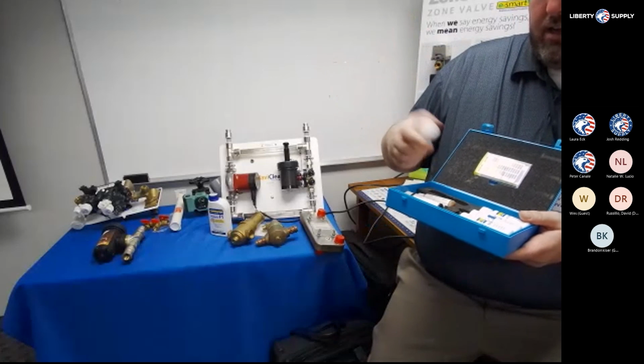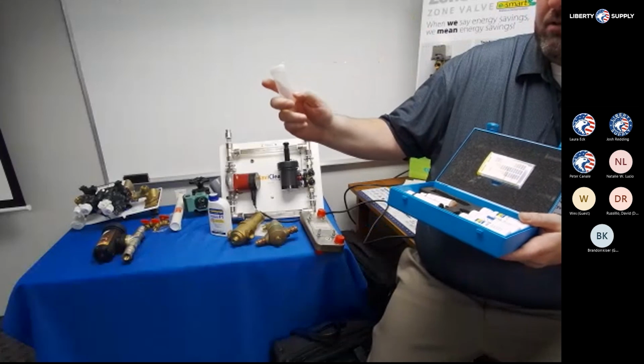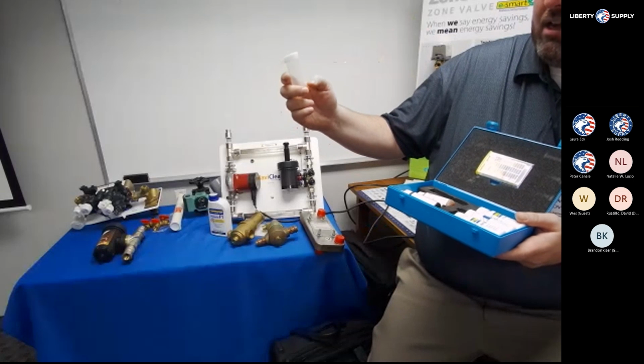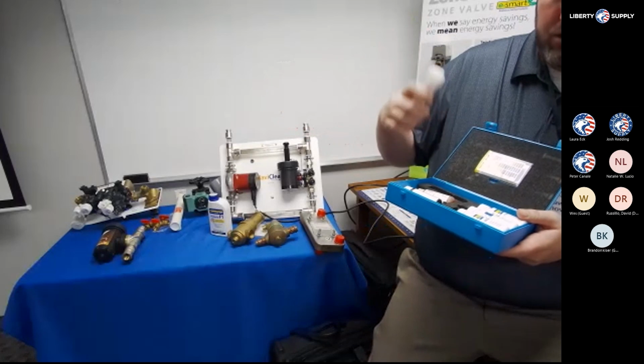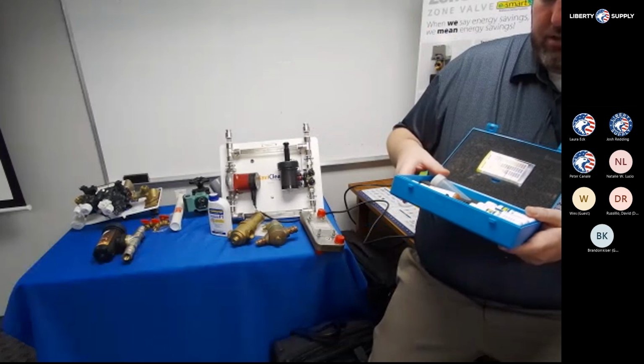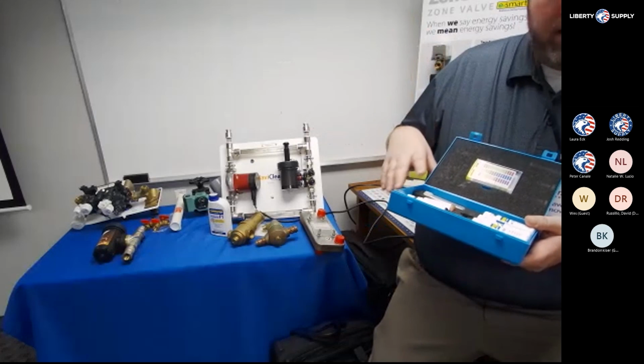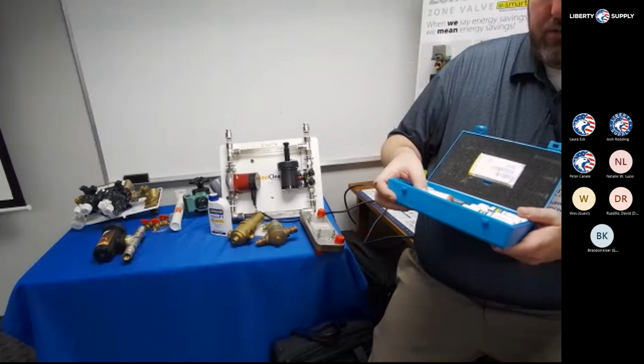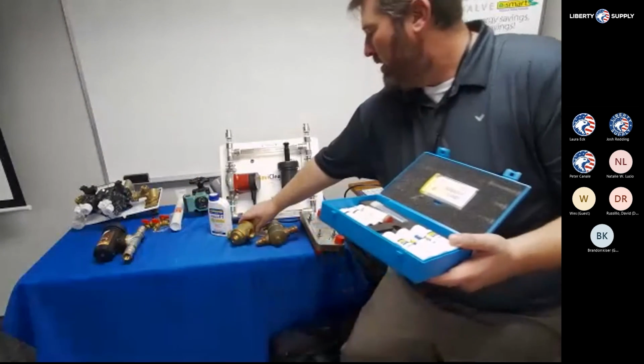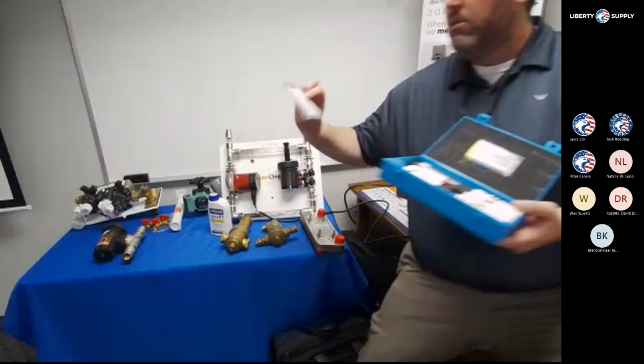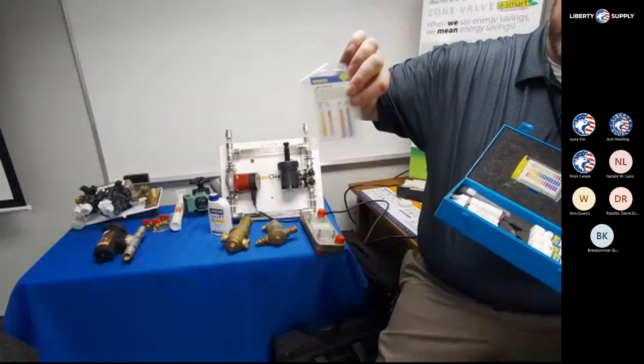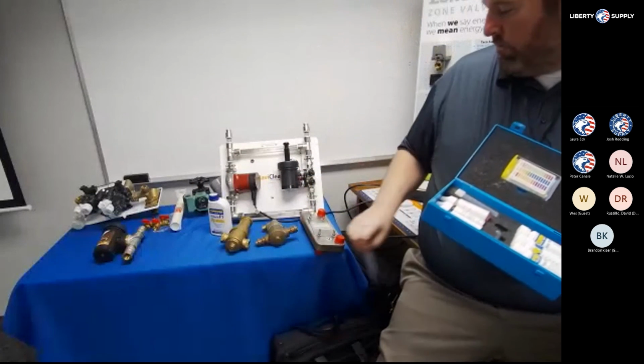If we're doing the F1 inhibitor test, you're going to go up there. It's marked here in milliliters. You're going to want to go up to 10, and then you're going to start doing your test. If you decide that you want some more training, we can go deeper on how you test for F1, or you can use the test strips, which we have here. This is what comes in the boiler commissioning kit. These are the test strips that we have for that as well.